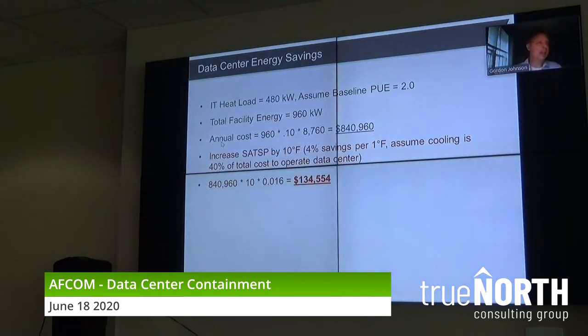How much money do we save by raising that temperature 10 degrees in this data center? Well, the third bullet point we've already established: it costs $840,000 to operate this data center. If you increase the supply air temperature by 10 degrees, there are a couple of rules of thumb, and I don't fully agree with the number I'm about to give you. Some in the industry will say a majority: for every degree Fahrenheit you raise your temperature, you're going to see a 4 to 5% savings on the total cost to operate your data center.